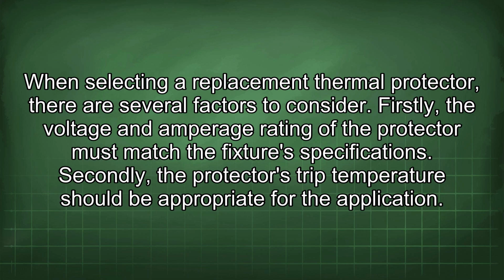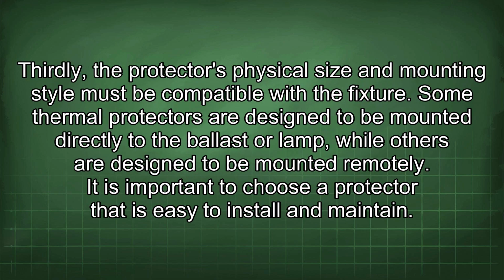When selecting a replacement thermal protector, there are several factors to consider. Firstly, the voltage and amperage rating of the protector must match the fixture specifications. Secondly, the protector's trip temperature should be appropriate for the application. Thirdly, the protector's physical size and mounting style must be compatible with the fixture. Some thermal protectors are designed to be mounted directly to the ballast or lamp, while others are designed to be mounted remotely. It is important to choose a protector that is easy to install and maintain.